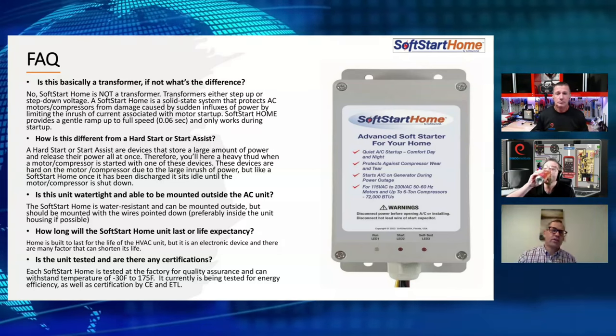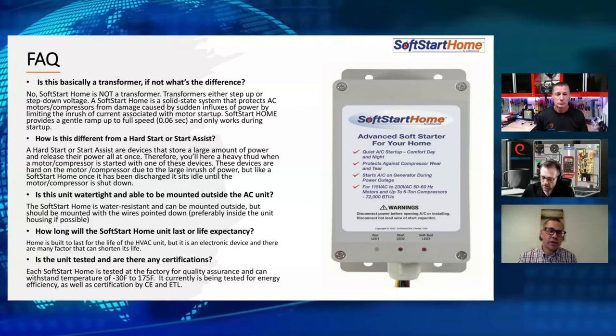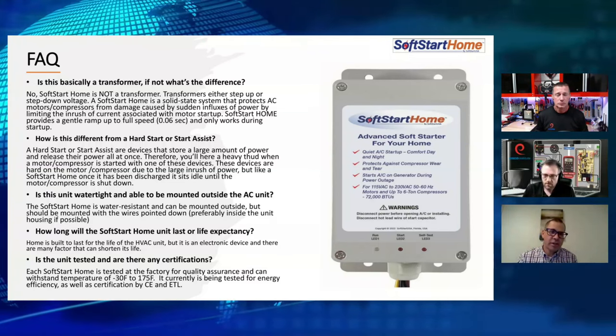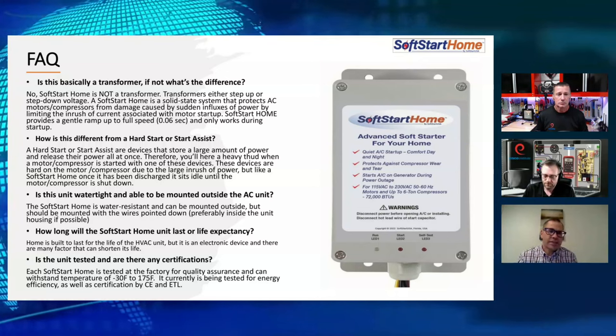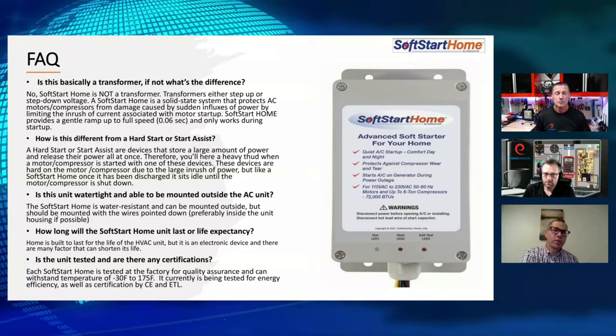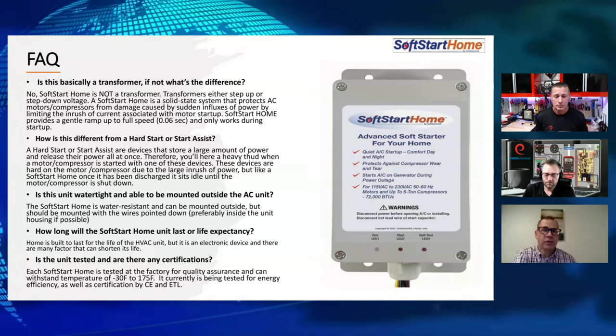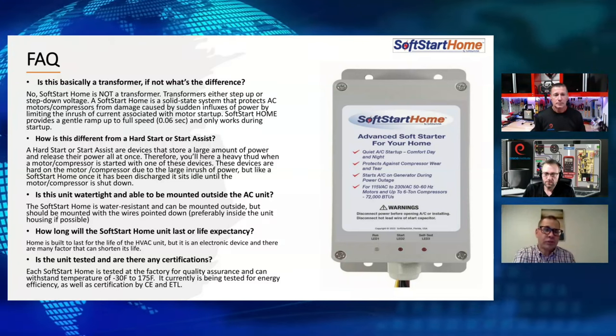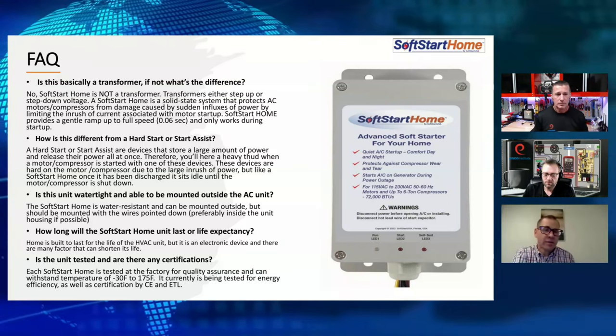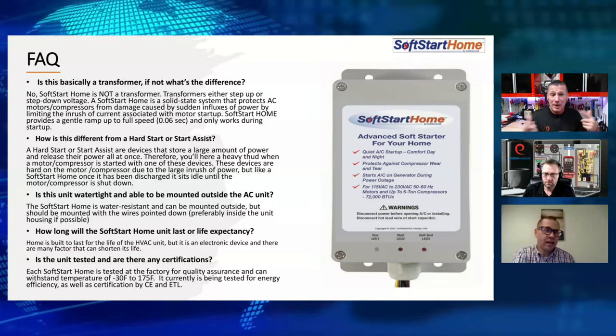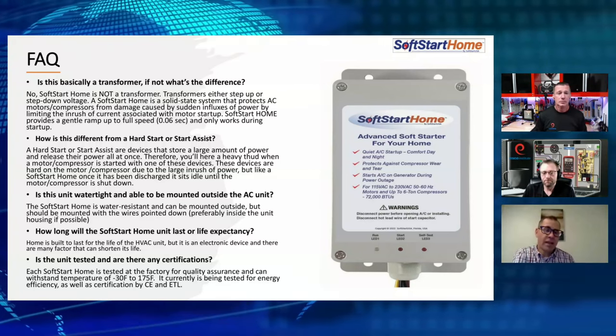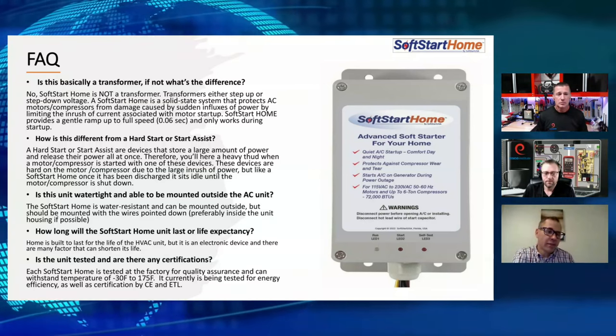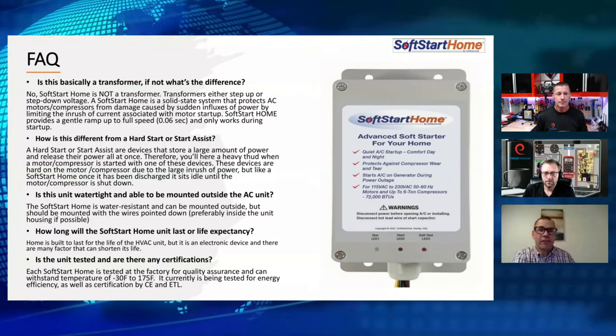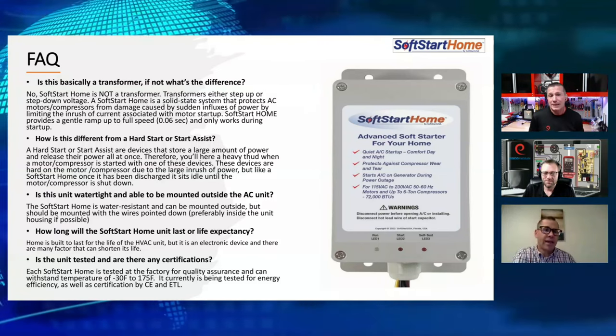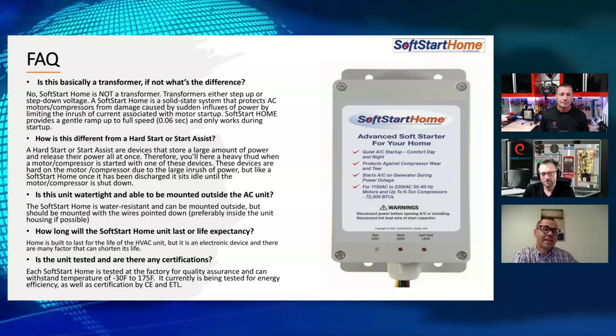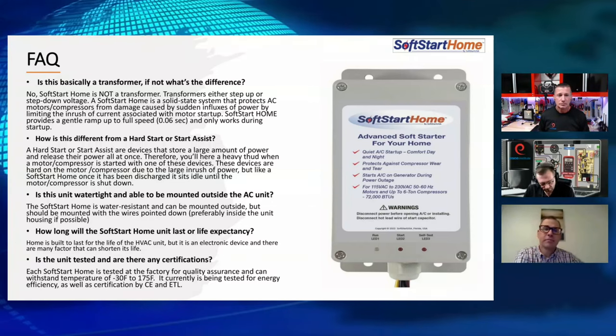A hard start is essentially a large capacitor. It's going to collect all that energy and release it all at once. That's really hard on the compressor, especially aging compressors. You're trying to extend their life, get them turning over a little bit longer. Hard starts can sometimes affect the longevity of that compressor. The soft start again is trying to extend the life by reducing that upfront stress.